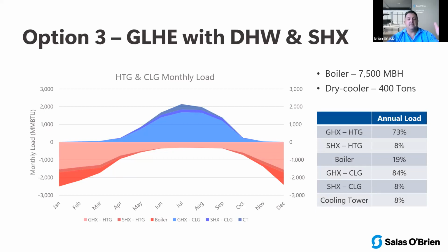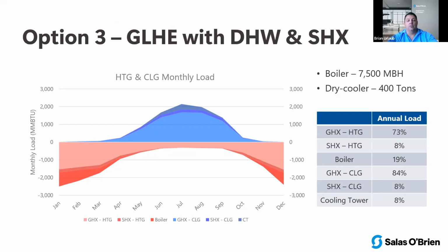Now, it doesn't mean cost-wise that that's going to be the end result, but from a theoretical application, what's the best we can do? These are all the technologies that we started to add in to get to where we wanted to be. And then the last thing we did actually, and I don't have a slide here, is we added thermal storage. And thermal storage was the biggest component to getting this basically to eliminate both the boiler and the dry cooler, other than maybe some redundancy for backup. But thermal storage was, I think, around 3 million gallons for a hot tank and then another 3 for a cold tank.